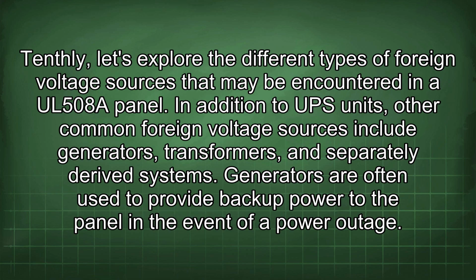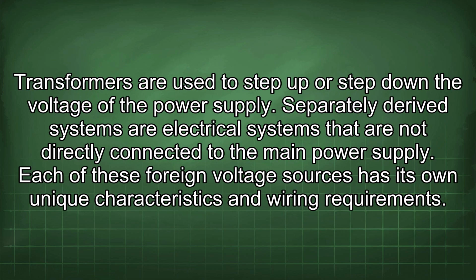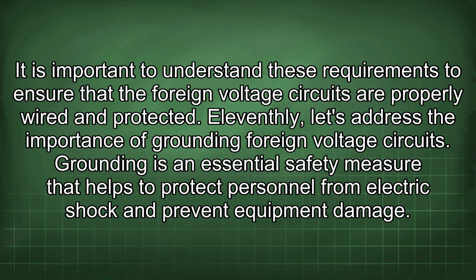Tenthly, let's explore the different types of foreign voltage sources that may be encountered in a UL508 panel. In addition to UPS units, other common foreign voltage sources include generators, transformers, and separately derived systems. Generators are often used to provide backup power to the panel in the event of a power outage. Transformers are used to step up or step down the voltage of the power supply. Separately derived systems are electrical systems that are not directly connected to the main power supply. Each of these foreign voltage sources has its own unique characteristics and wiring requirements. It is important to understand these requirements to ensure that the foreign voltage circuits are properly wired and protected.